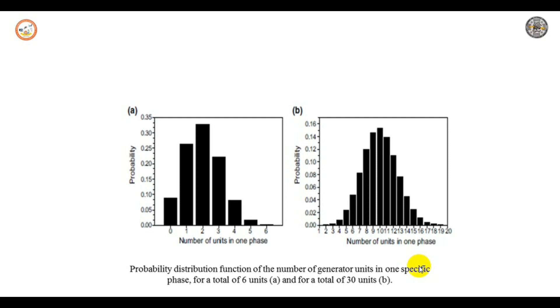So I am talking with respect to this. These calculations have been performed when a total of 6 units are connected to the feeder, and when a total of 30 units are connected to the feeder. In both cases, 100,000 simulations were performed to obtain the estimate of probabilities. For 6 generators, the number of units connected to one phase varies, with 95% confidence, between 0 and 4. For 30 units, it varies between 5 and 15.